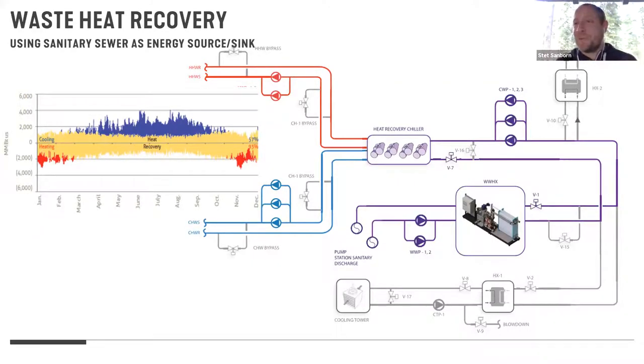And it's actually a pretty quality source, both in cold conditions and hot outside air conditions. So in the wintertime, when it's really cold outside, that source is warmer than outside air temperature, so we get an improved COP. Right. And in the summertime, when the outside air temperature is hot and humid, we also see improved performance because that source is now cooler than outside air temperature. So it works, it's a benefit in both seasons.